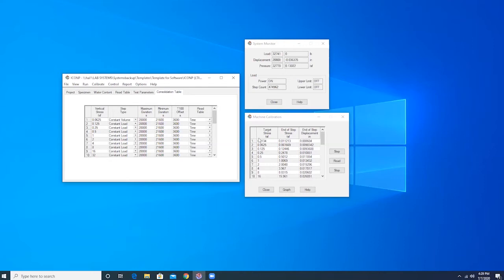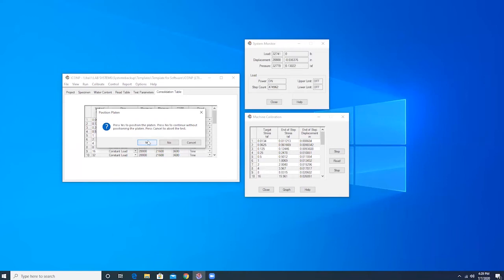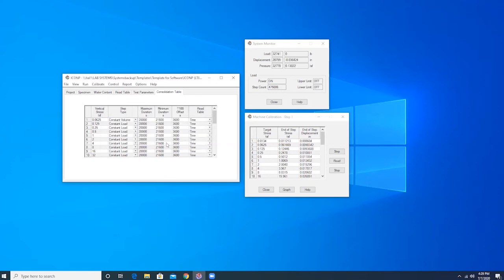Next, in the machine calibration table, click Step. Position Platen will pop up. Click Yes. Give some time for the machine to adjust. The position platen function is a procedure where the machine brings the sample into contact with the load cell. When it touches the load cell button and a very small load is applied, also known as the seating load, it will automatically stop.